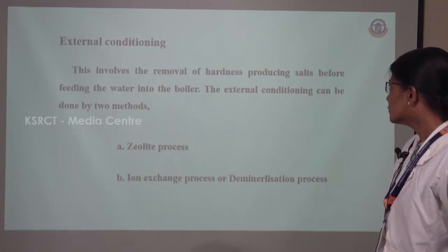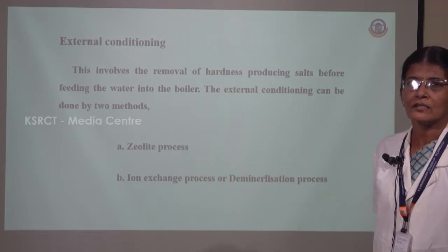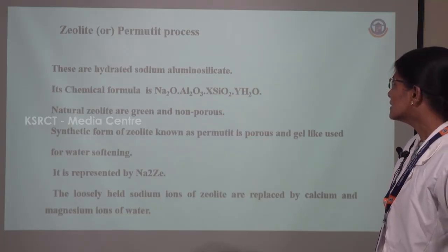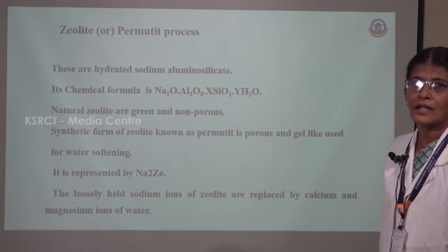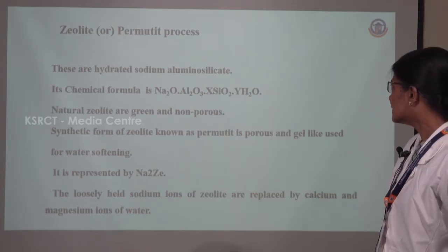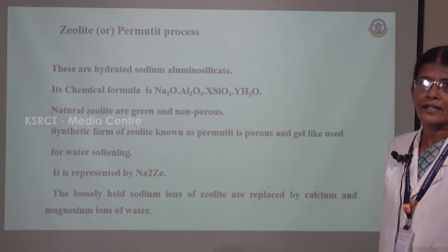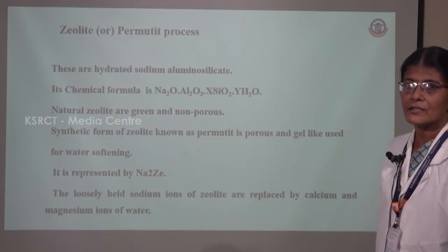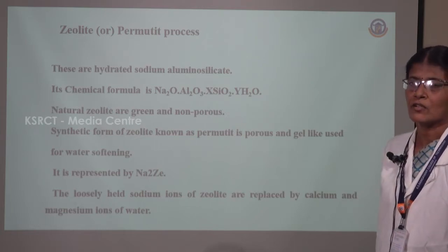External conditioning is usually done by two methods. The first method is the zeolite method. The second process is the ion exchange process, also called the demineralization process. Zeolite is hydrated sodium alumino silicate. Its chemical formula is Na₂O·Al₂O₃·xSiO₂·yH₂O. Natural zeolite is usually green in color. It is non-porous, and therefore we use the synthetic form of zeolite, known as permutite, which is porous in nature and gel-like in structure, and therefore it is used for water softening.